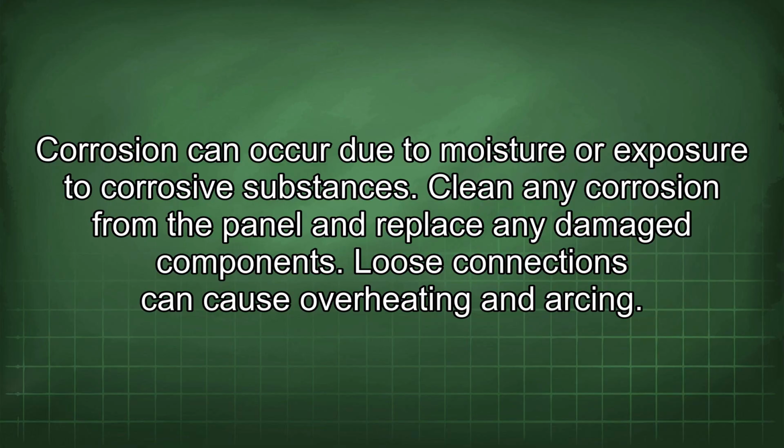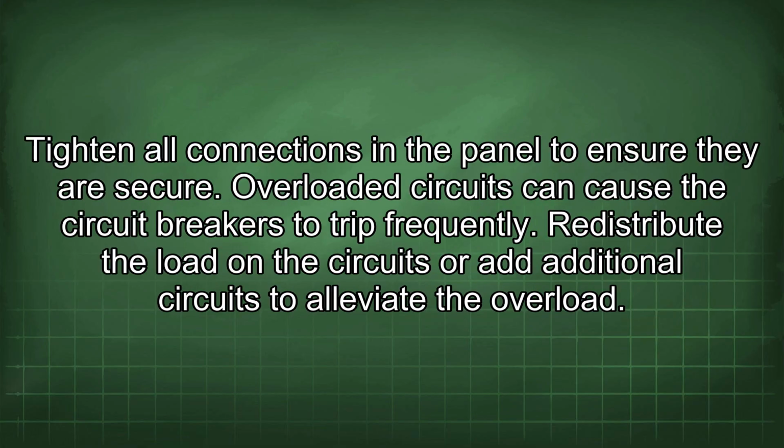Loose connections can cause overheating and arcing. Tighten all connections in the panel to ensure they are secure. Overloaded circuits can cause the circuit breakers to trip frequently. Redistribute the load in the circuits or add additional circuits to alleviate the overload.